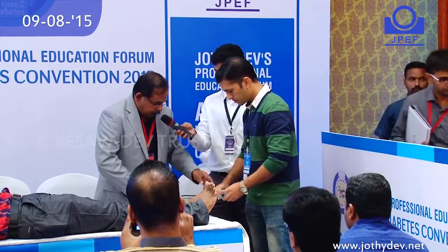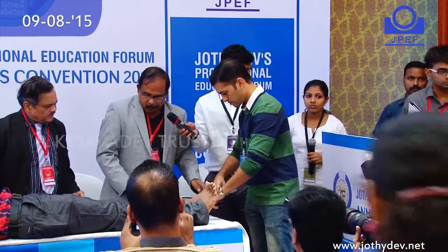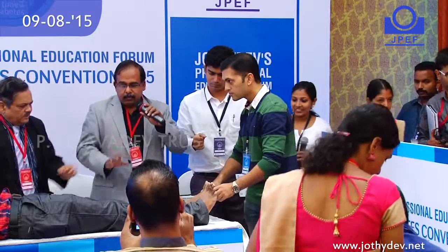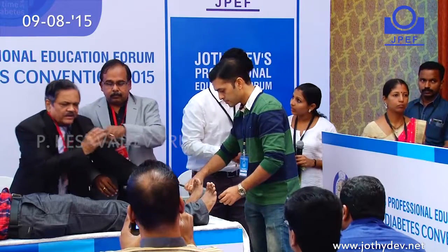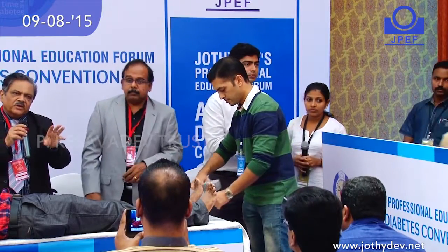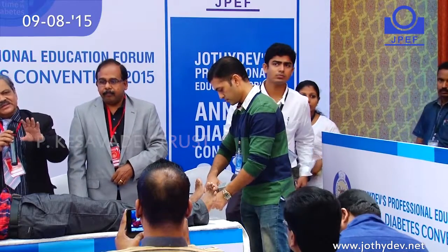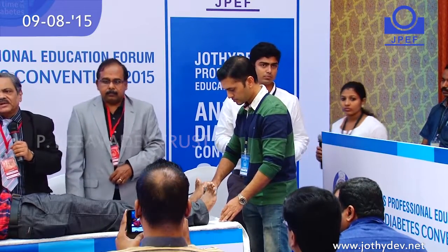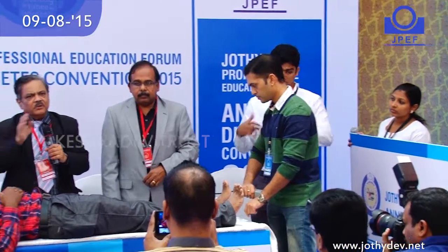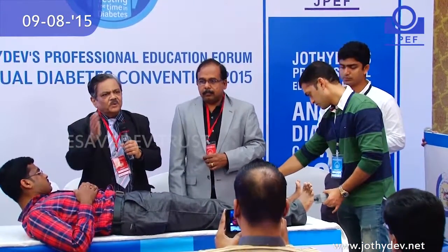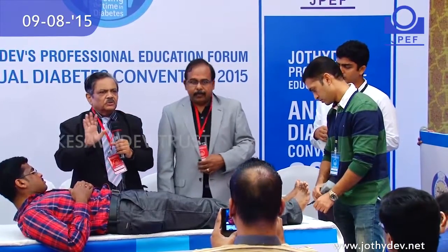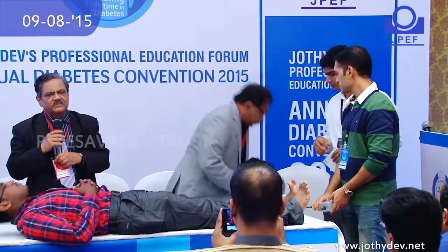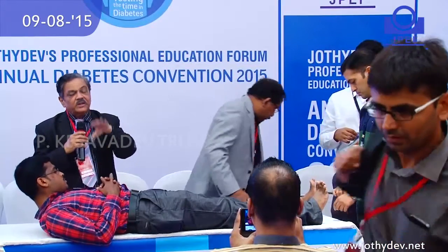Just do it. I will start with 5, right? Okay. So it's very simple. The simple principle is that this vibrates, and the vibration is converted to a number. We express it in millivolts as an absolute number, very easy. So if it is above 25, we say definite neuropathy. Between 15 to 25, prone for neuropathy, and below 15, there may not be neuropathy. That's how we screen everybody. As the vibration sense is carried by the large fibers, this is a large fiber neuropathy where you get the vibration sensation loss.